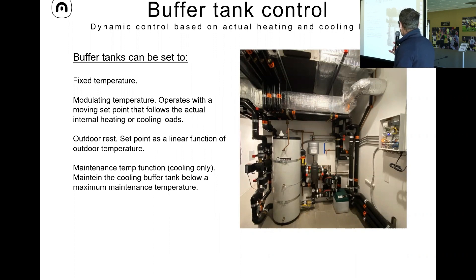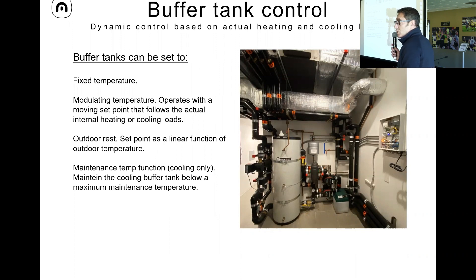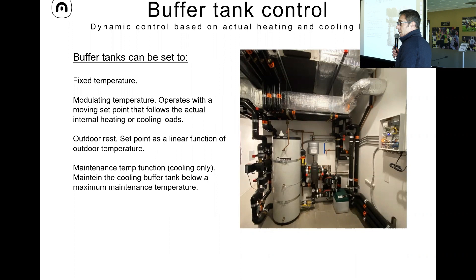There are different ways to control the buffer tank temperature. Fixed temperature — you keep it at 10 degrees for cooling, or with a four-pipe system at 10 and 40 degrees for heating and cooling. But the way I like to control it is with modulating temperature, which allows you to optimize heat pump performance. The modulation is based on internal heating and cooling loads — we estimate the real loads in every single room, and that dictates the real temperature needed in the buffer tank. There is also an outdoor reset function based on a set point and outdoor temperature.